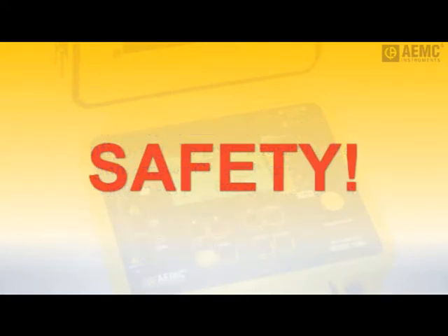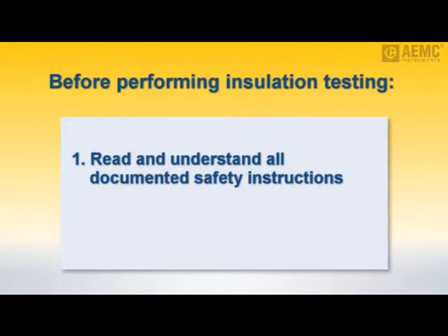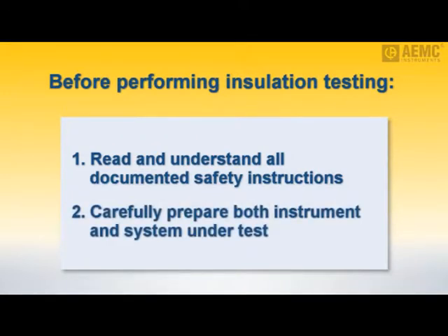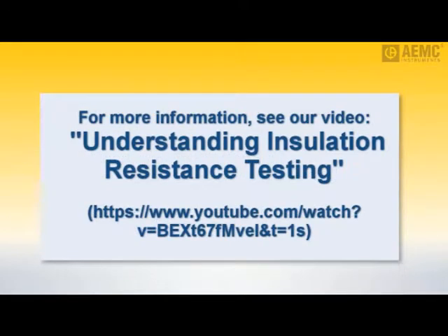Before we begin, let's pause to talk about safety. Before performing any insulation resistance test, be sure to observe all safety instructions specified in the documentation that comes with your test instrument. Insulation resistance testing involves the application of high DC voltages. Therefore, carefully preparing the system under test and the instrument is crucial to your safety and helps prevent damage to your wiring and machinery and personal injury. For more information, please see our video, Understanding Insulation Resistance Testing, available on the AEMC YouTube channel.